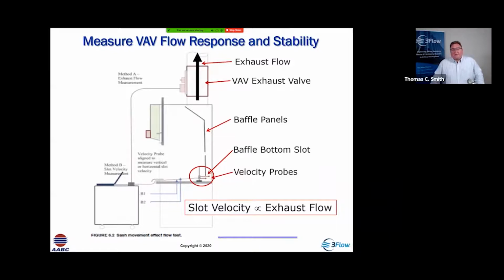So looking at this evaluation, we could measure the flow in the duct. We could take the flow off the flow sensor if there was one equipped on the VAV, but oftentimes it's very hard to gain access to the duct or the controls. But we find that the velocity through the slot in the baffle is proportional to the flow through the duct. So the velocity here, Q equals VA, is proportional to the exhaust flow. If we can measure the velocity in this slot, we can use that to correlate the flow and then determine, as we raise and lower the sash, how that's modulating flow.